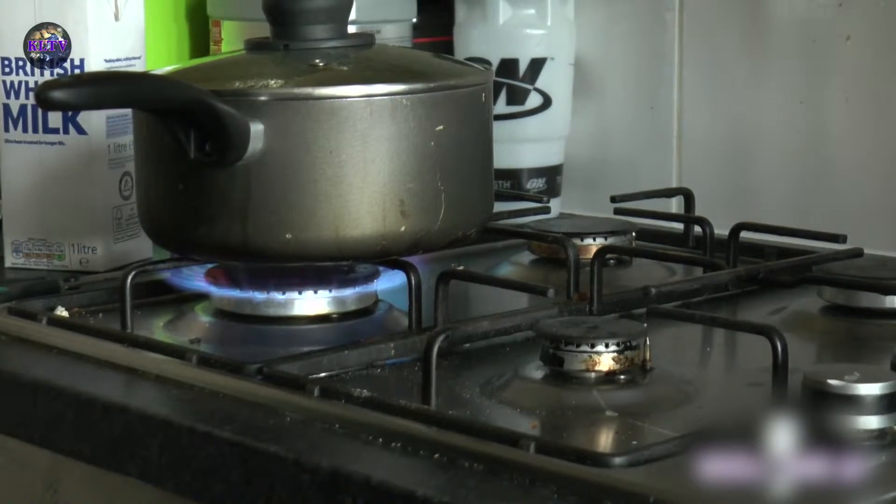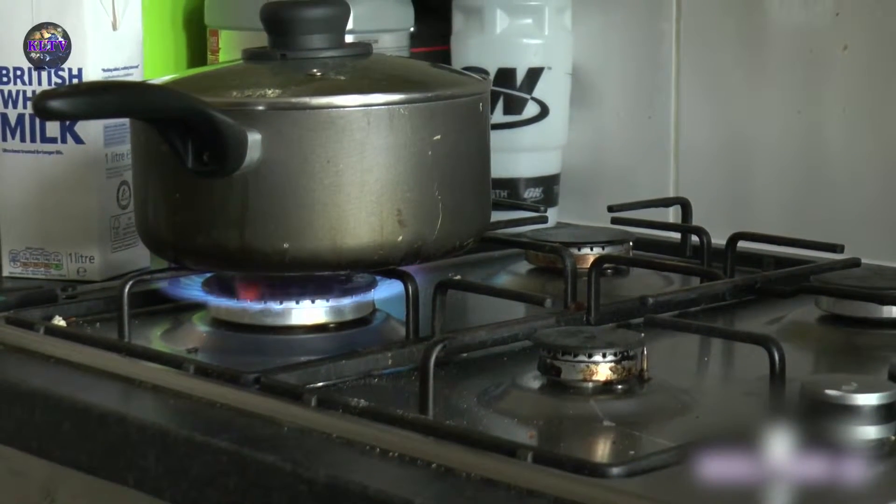It isn't just the gas appliances — it's actually the ventilation into the room. There are some visible signs on appliances: a yellow flame perhaps looking a little bit loose rather than a nice blue flame, and signs of sooting around the appliances where you end up with deposits, are all indicators that carbon monoxide may be present.